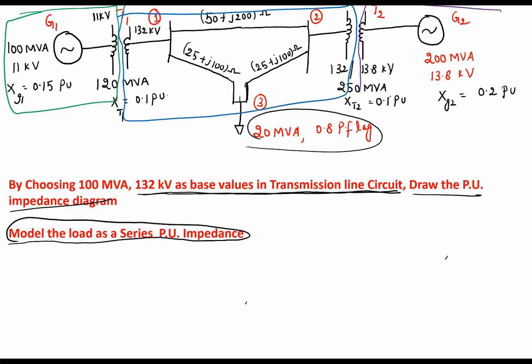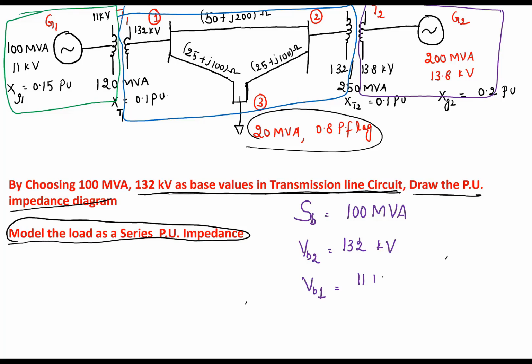So this is the third section. Okay, so we know the base voltage in which section? Section 2. So our base MVA in the problem is SB equals 100 MVA, which he has given, and VB, the base voltage in the second section, is 132 kV. Now, what is the base voltage in the first section? Let us call it VB1. Since our base voltage is matching with the transformer voltage, we can directly write VB1 is 11 kV. Similarly, if you apply those formulas, you are going to get VB3 as 13.8 kV.